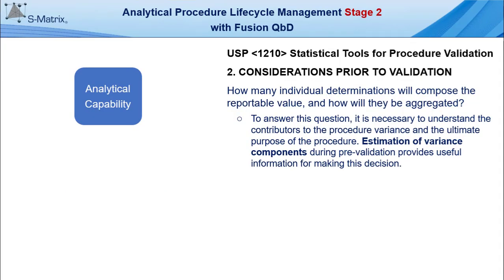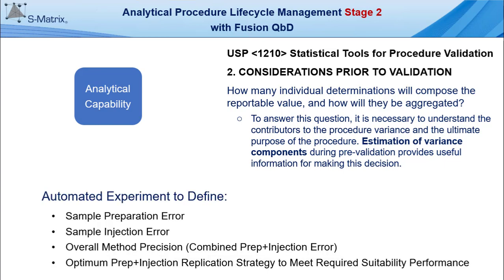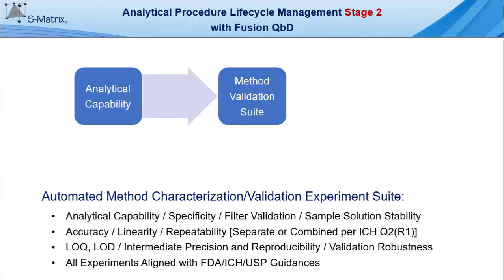Continuing with APLM stage 2, the analytical capability experiment within Fusion QBD's method validation module enables the user to quickly define the components of variation described in USP 1210, including sample preparation error, sample injection error, overall method precision, the combination of prep plus injection error, and the optimum prep plus injection replication strategy to meet required system suitability performance requirements.